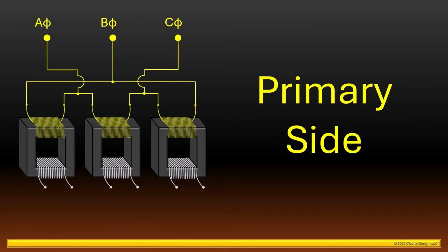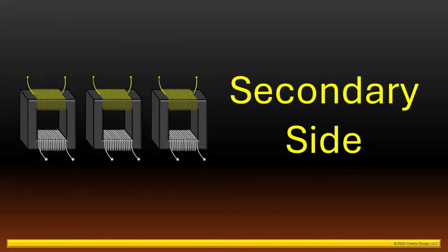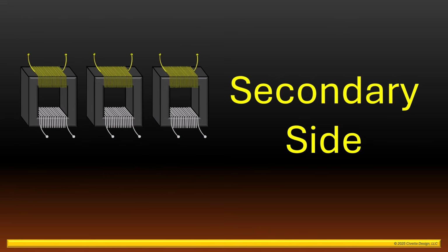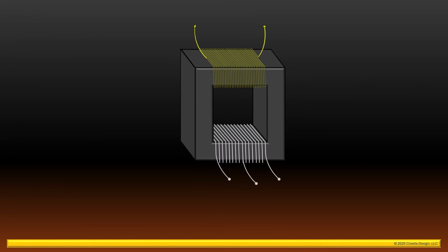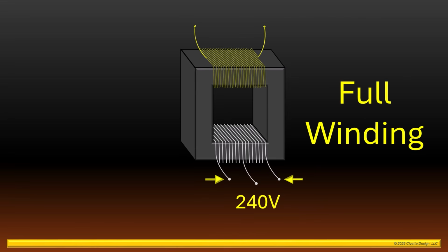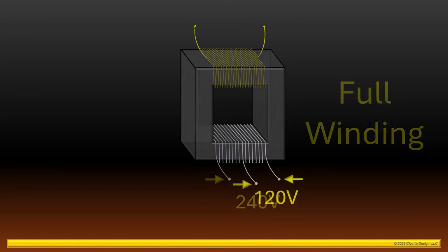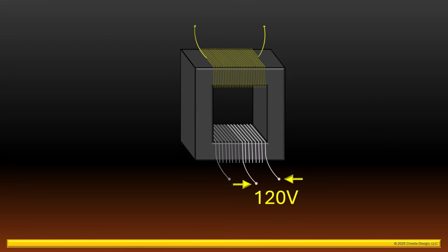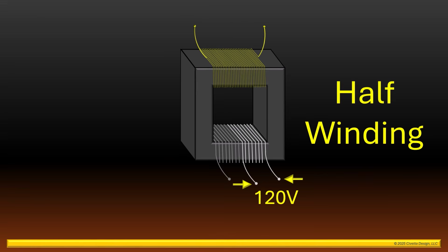Now that we've completed the delta connection on the primary side of the transformer bank, let's move that aside and take a look at how the secondary side is going to be connected. Before we do, though, let's take a look at the secondary windings in this transformer for a moment. We already know the transformer produces a secondary voltage of 240 volts across the full secondary winding. The Y connection we're going to look at only utilizes the 120 volt potential between the center tap and one of the phase leads, using only 1/2 of the winding.